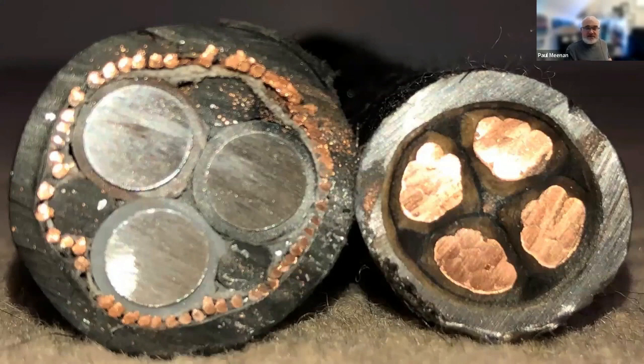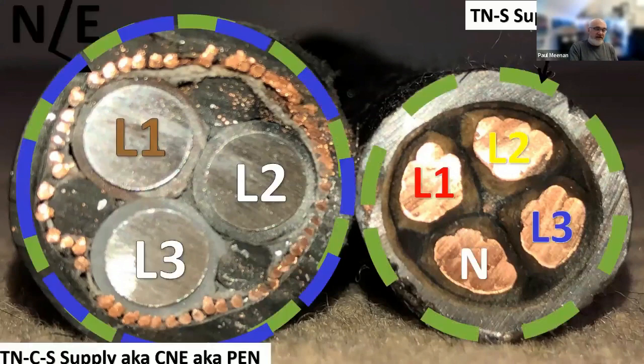So this is actually a picture, one of my favorites. It was taken by me, and the cable on the right is a lead sheath cable. So this was installed in the 30s. And what you have is effectively 3 phases, L1, L2, L3, and a neutral. And the lead sheath is a wonderful low impedance earth conductor. The one on the left is the modern cable installed in the 70s, which had a 40-year design life.